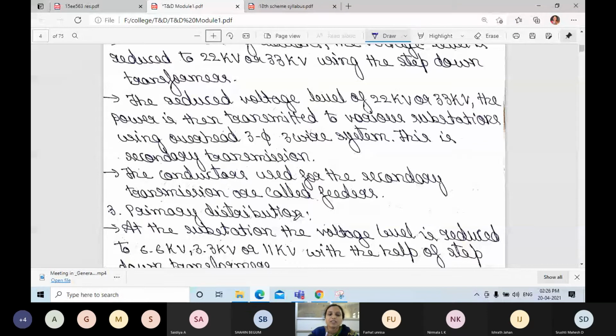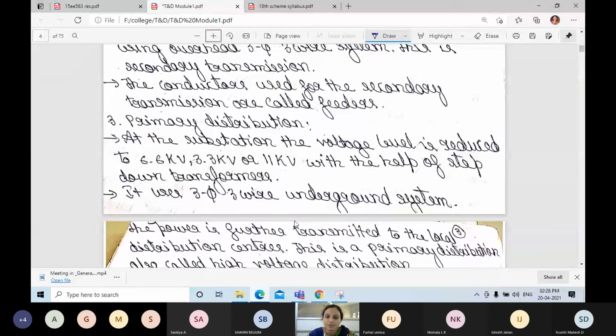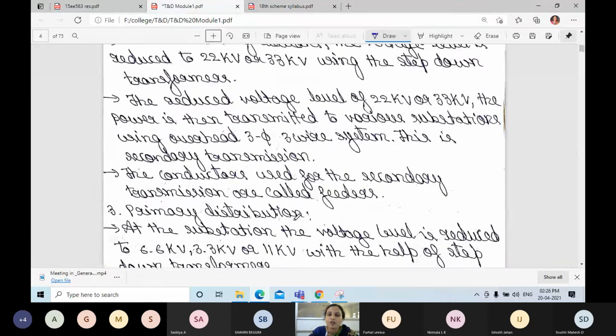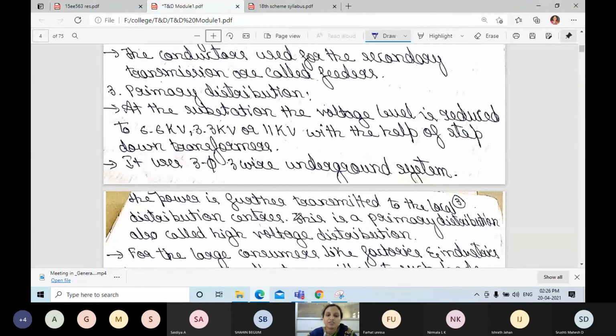Next, primary distribution. In secondary transmission, the final voltage we got is 33 kV, reduced from 220 kV to 33 or 22 kV. Here in primary distribution, from 22 or 33 kV, we reduce the voltage level to 6.6 kV, 3.3 kV or 11 kV using a step-down transformer. Here also we use a three-phase, three-wire system.